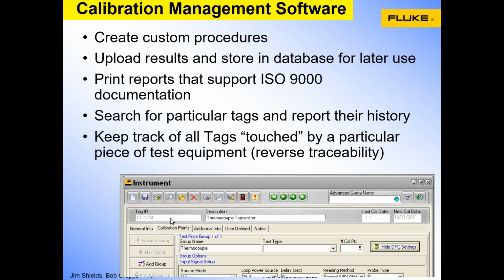In the event that it does, you might want to ask the question, which instruments did this calibrator touch while it was in the field and deployed by a calibration technician? Reverse traceability allows you to use the software to find which tags in the plant were touched by that calibrator, in order, beginning with the most recent to the least recent. You can then go through and recheck those instruments to ensure that they're within specification, and if not, remediate and adjust them to within specification, of course with a fresh calibrator that you know has a good calibration on it. So reverse traceability is the tool that allows you to solve any problems that may have been caused by the errant performance of the out of tolerance calibrator.